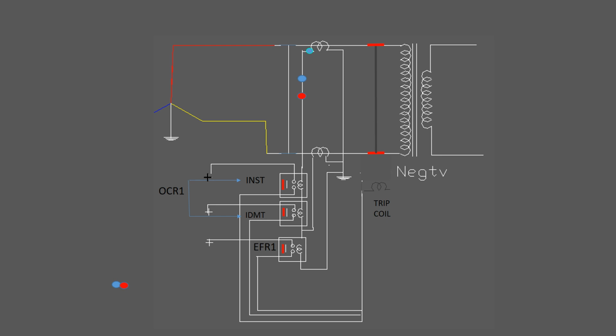So already we have seen the setting for the 21.6 MVA power transformer, with 400 by 5 CT ratio on the 132 kV side and 1500 by 5 on the 27 kV side. The rated load current on the 132 kV side is how much? It is 163.6 ampere. I have made a mistake. The rated IDMT setting of the rated load current on the 132 kV side is 190%.